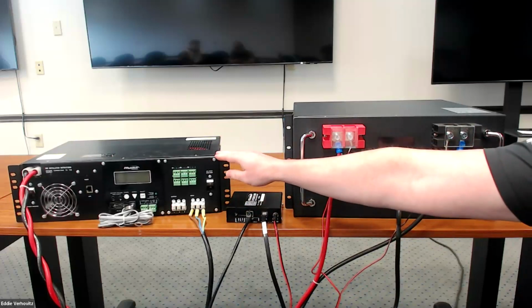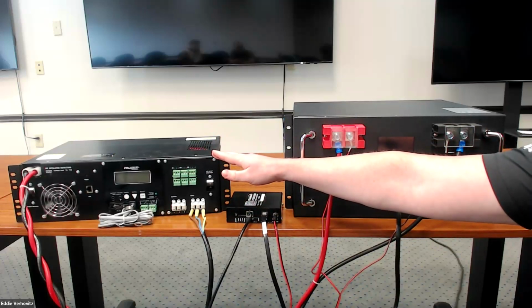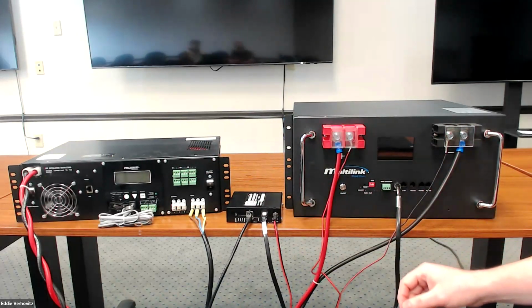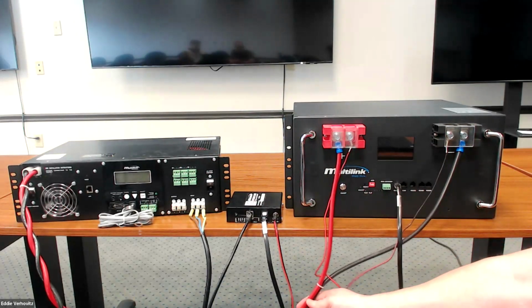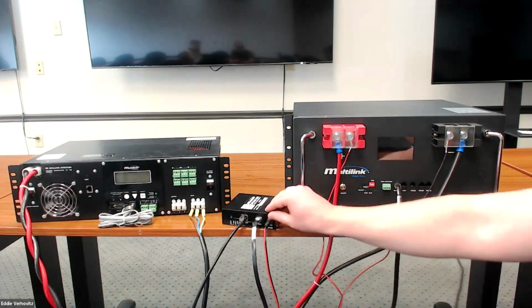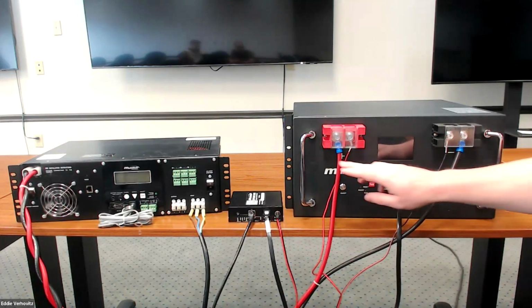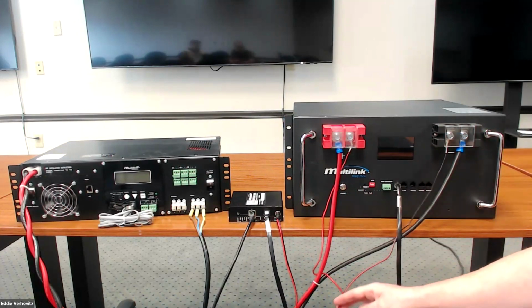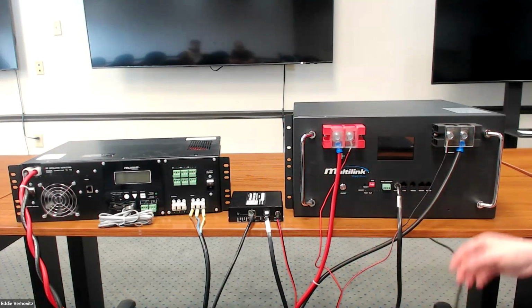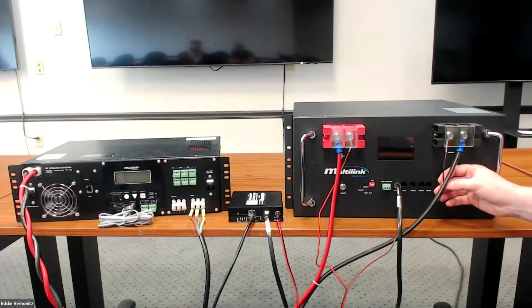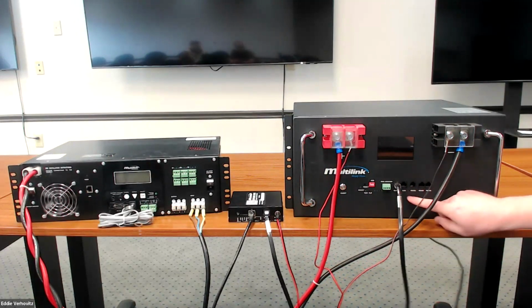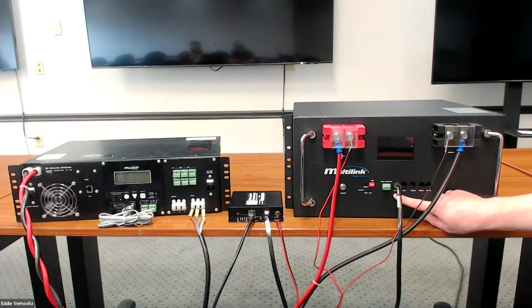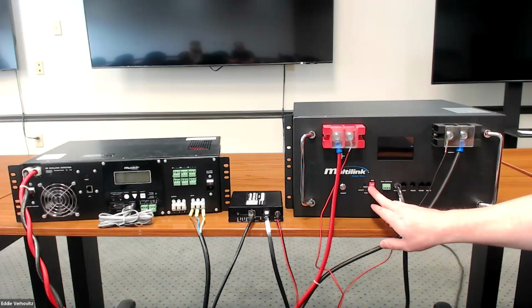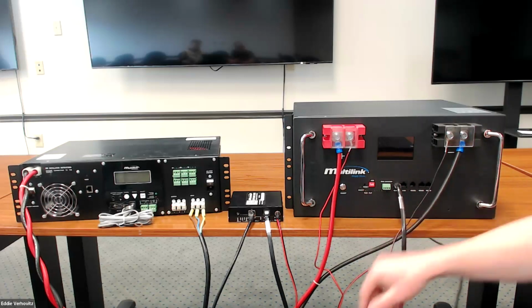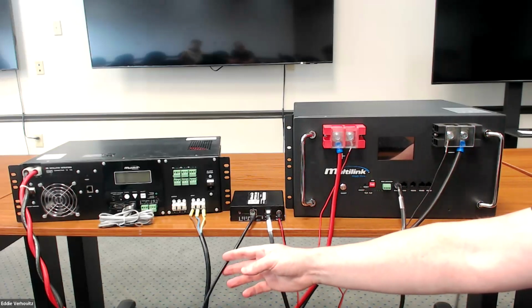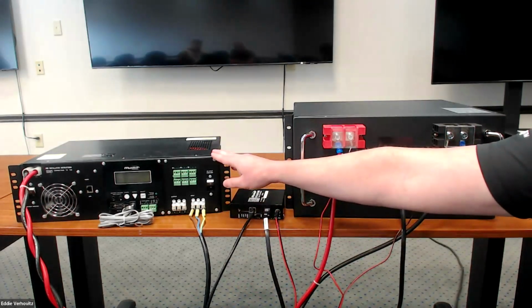And we have our EP1100, which is our 48 volt UPS system. As shown in the wiring diagram in the PowerPoint presentation, we have our main power harness wired directly to the terminals, with correct polarities. Because we are using the Multilink BMS, its power harness is also wired to separate terminals on the battery. We have our serial cable connected to the leftmost port of our RS-485 ports, with our address set to 1. We have our Ethernet connected to the laptop, and an AC power source available for the EP1100.